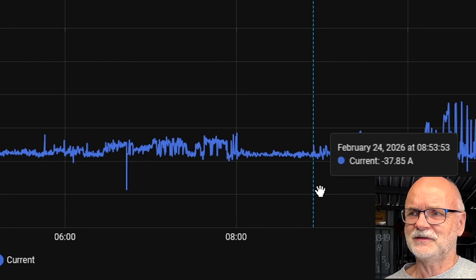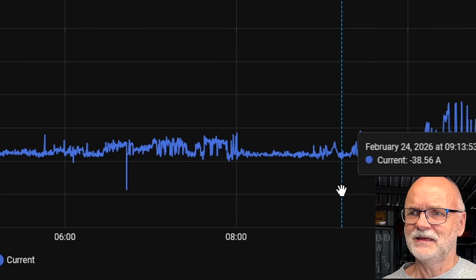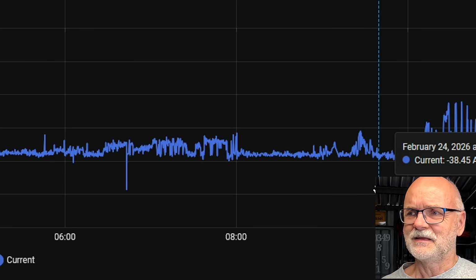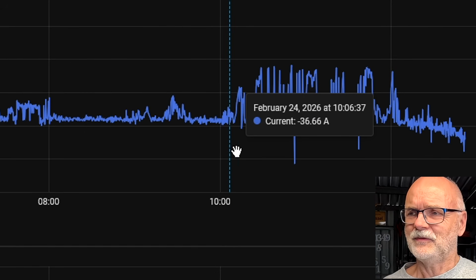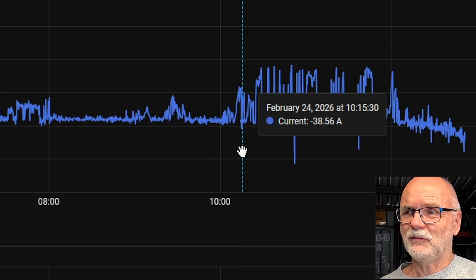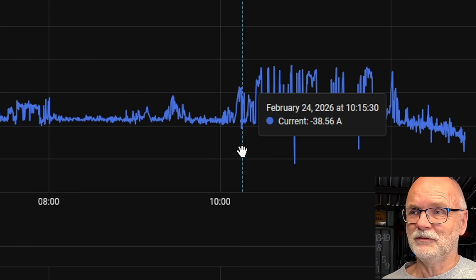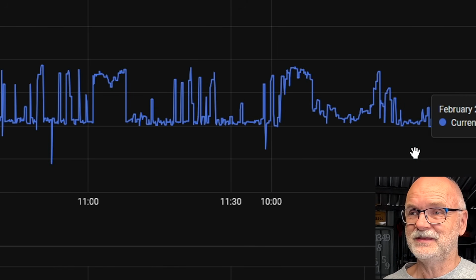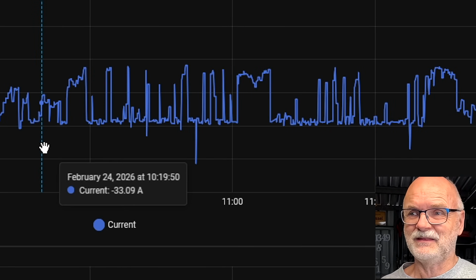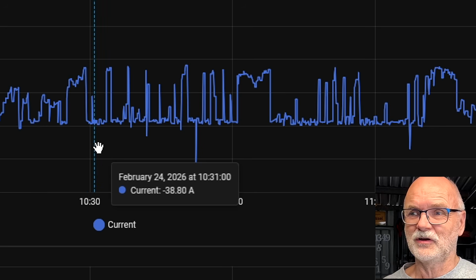Very constant discharge current, 38 amps, and we've got these spikes. Here's a big one, and this is always when the current coming from the inverter is going down, so we're discharging the battery less. It's even more apparent here from around 10:30, 11 o'clock.